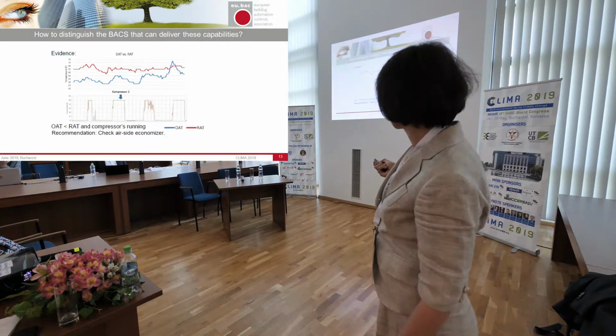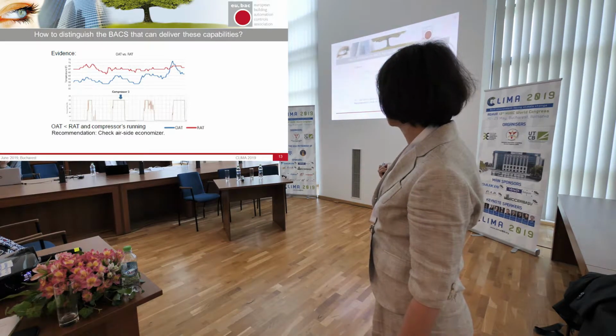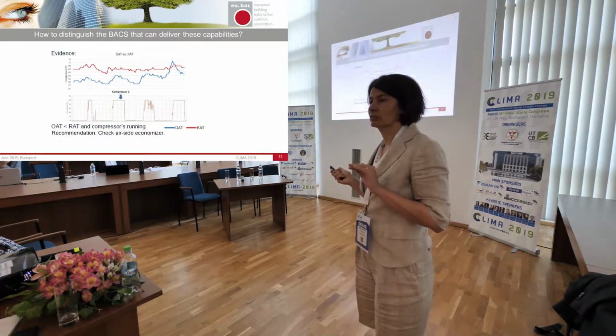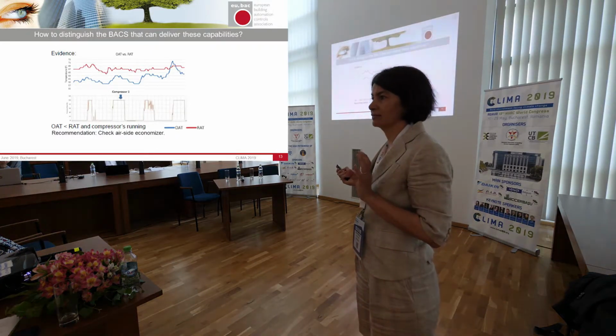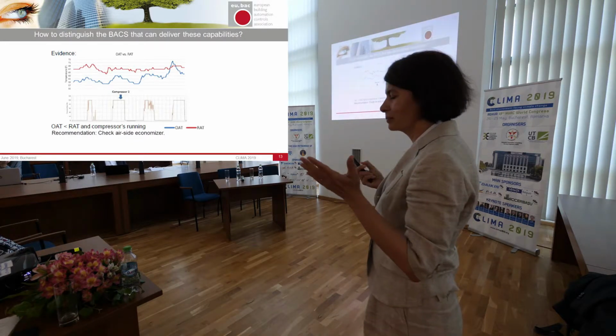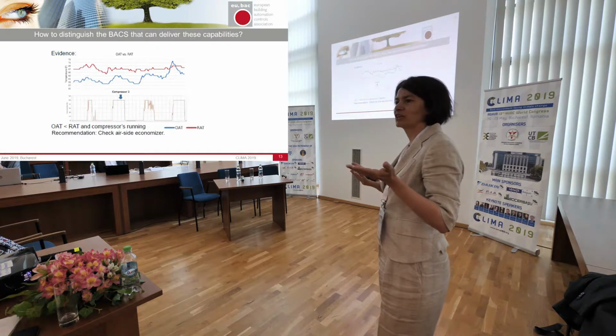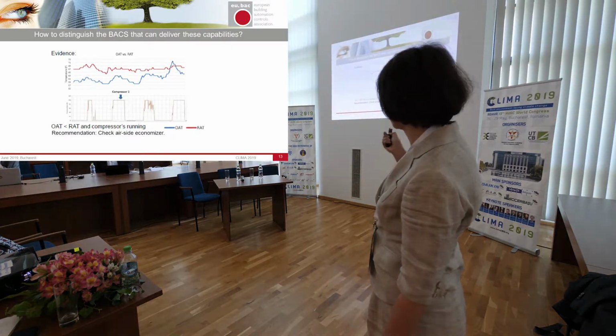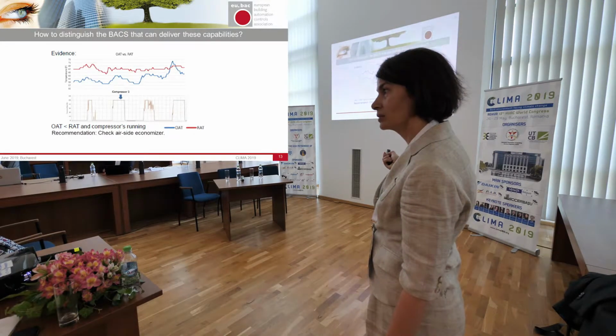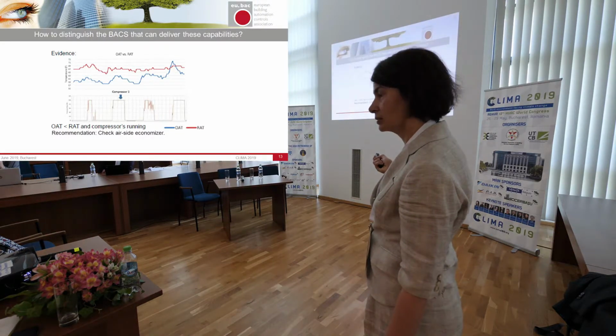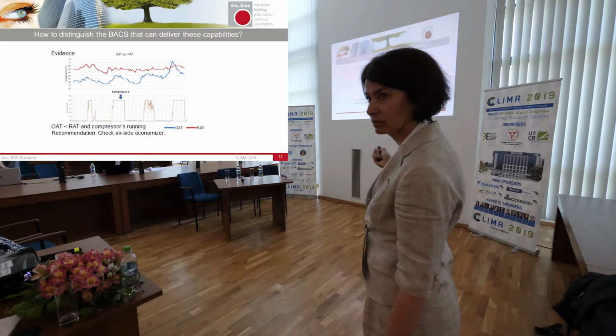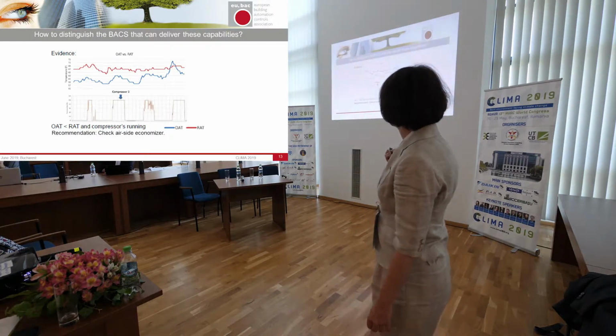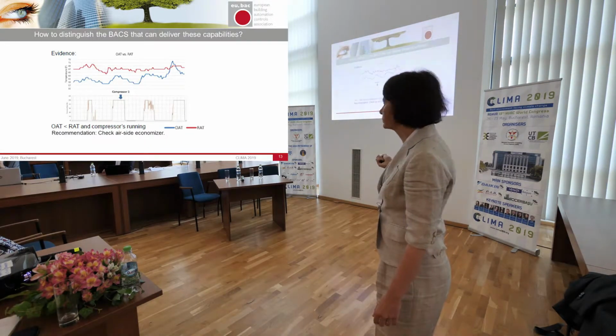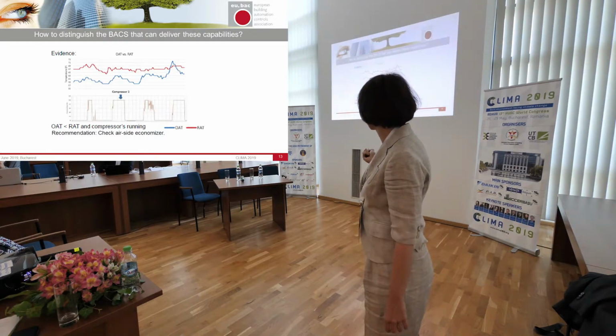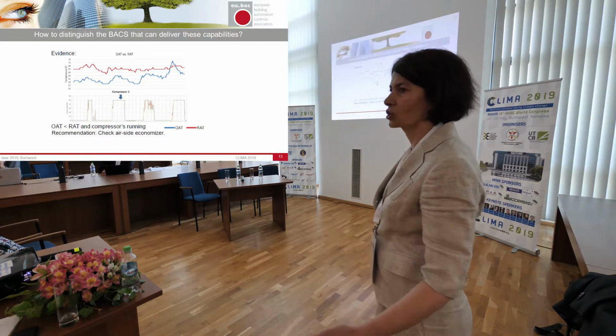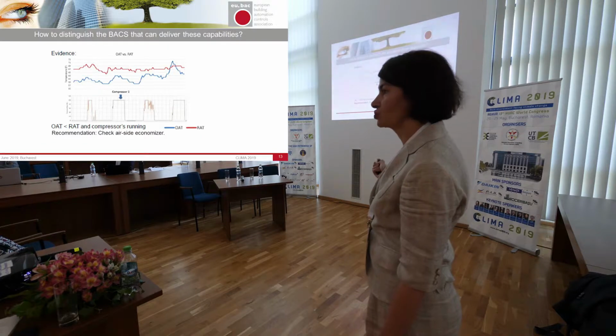And then group B, it actually says, okay, the outside air temperature is lower than the return air temperature, but my compressor is running. So something is not that efficient really. And depends on the circumstances, so if it is a fairly new building, let's say, and that has been operating properly before, this specific control sequence: if the outside air temperature is lower than the return air temperature, then I don't run my chillers, I use the free cooling. Then there must be something wrong with the airside economizer, that's what it's called in America, but that means, in this case, the dampers, something's wrong. So first thing is, go and check what that is.